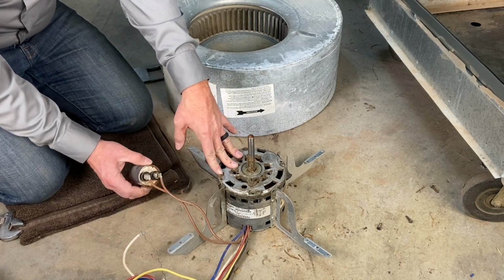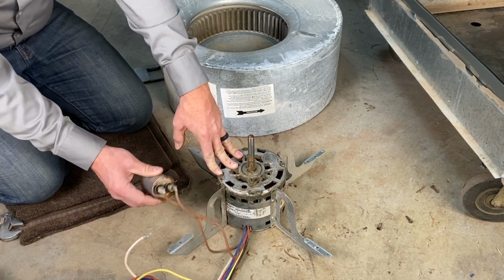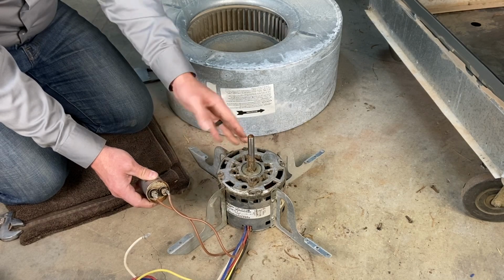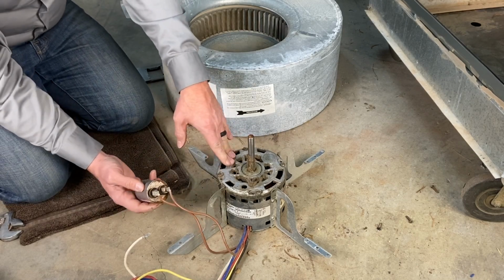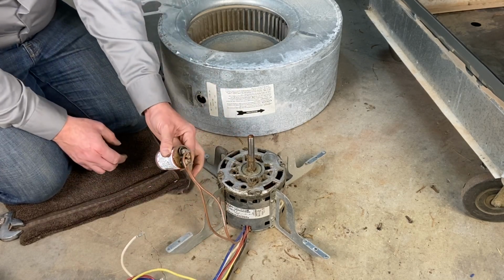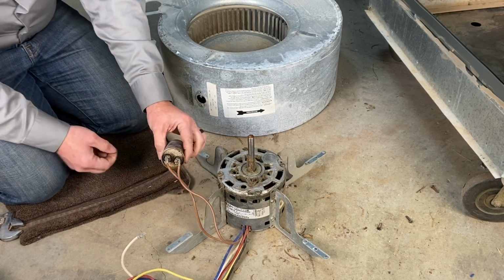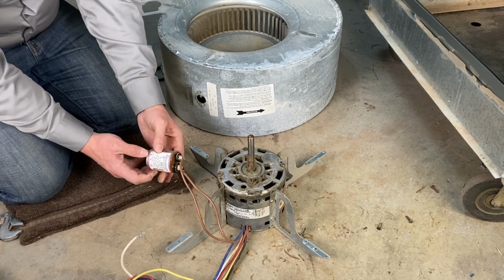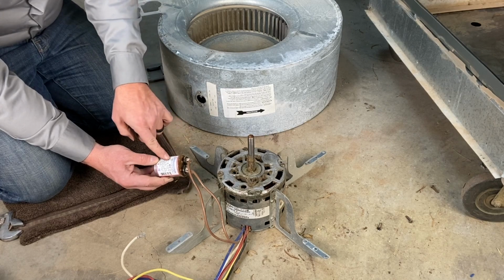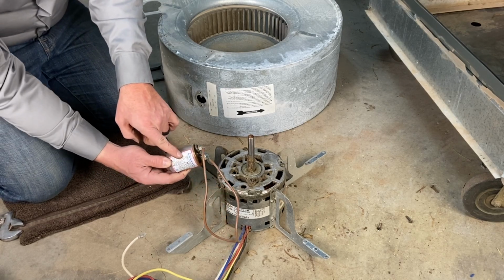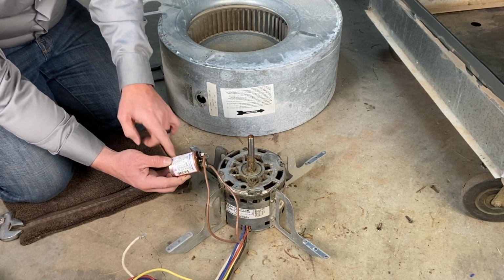Anytime you change a blower motor, you also put a new capacitor in. Usually the new capacitor is going to be a different size for the motor anyways. But if my motor's good, I also want to check my capacitor. So I'm going to discharge it with a 20,000 ohm 5-watt resistor, then pull the wires off and make sure it reads correctly. This one's rated for a 7.5 microfarad capacitor.